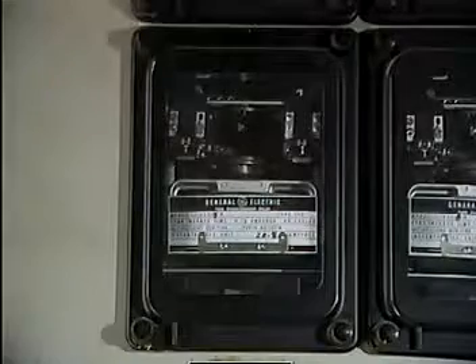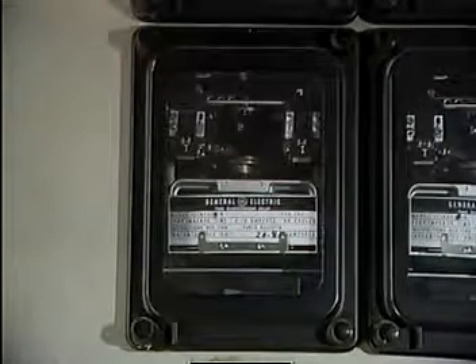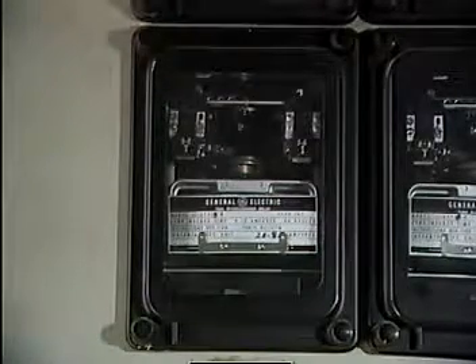Some breakers have internal devices, such as electrical coils, that sense excessive current and open the contacts. Other breakers use separate external devices called relays to do the same thing. Relays sense abnormal circuit conditions and send a signal that trips the breaker.